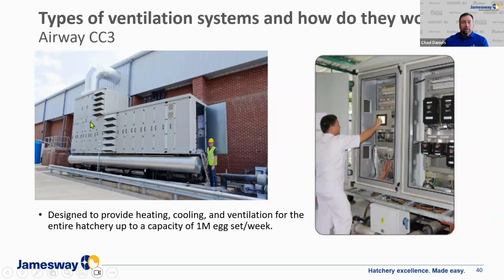So the next type of ventilation system that we see in the market today is referred to as a CC3. It's a climate control with 3 solutions. Essentially, it's providing all the ventilation into the hatchery. It also has all of the tanks built into the unit. The controls are built into the end of it. It has heating and cooling built in, and it has the ability to do heat recovery and dehumidification. So essentially, it's the modular system, all built into one unit. And a lot of times hatchery applications will utilize 2 or 3 of these Airway systems for just one hatchery, depending on the size of the facility.